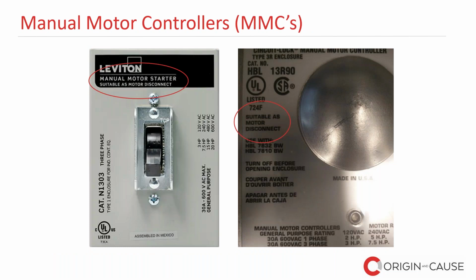Next, I want to talk about manual motor controllers, or as we call them, MMCs, and these are more typically used in commercial settings. If you look at the left picture, it looks like a light switch for all intents and purposes, except it has a much larger load and a much bigger use. You can use it to turn on and off a motor and a system, maybe possibly a whole line of product on a commercial line. And the intent of it is only basically to use as a switch to turn on and off.